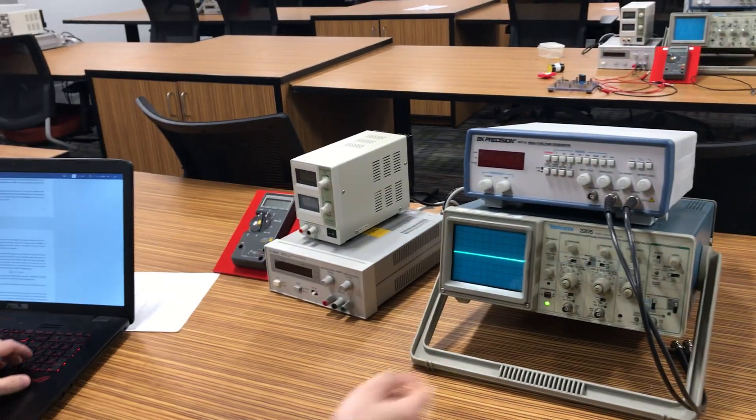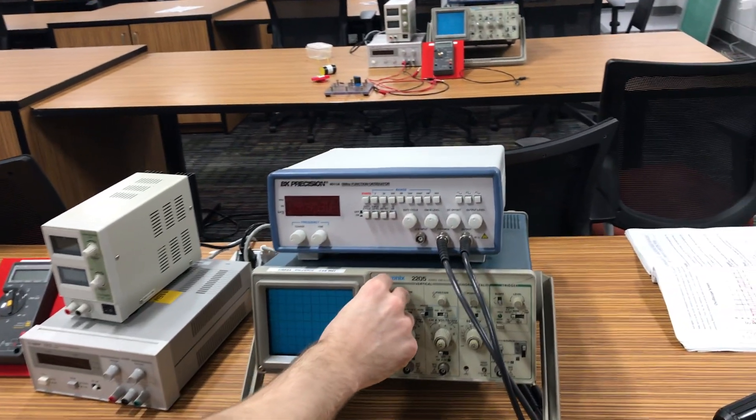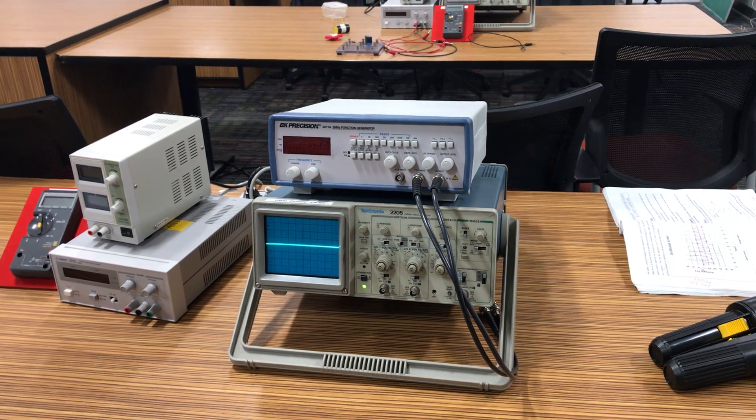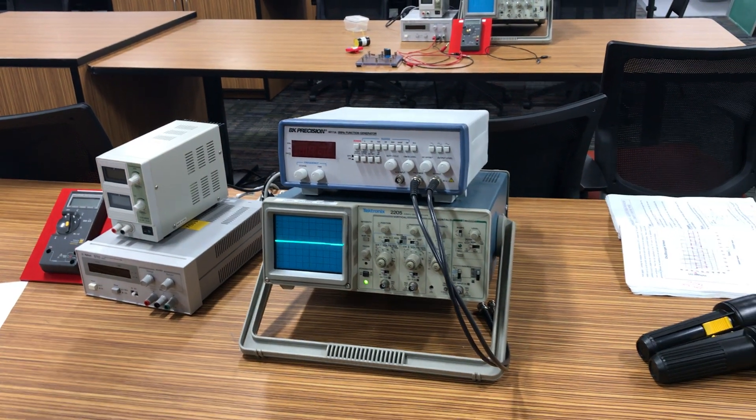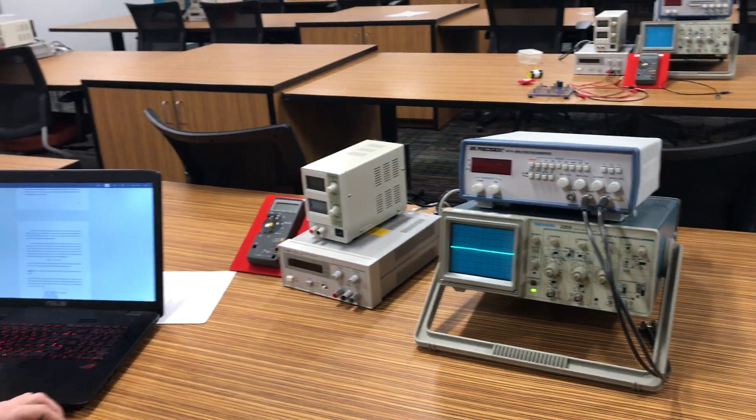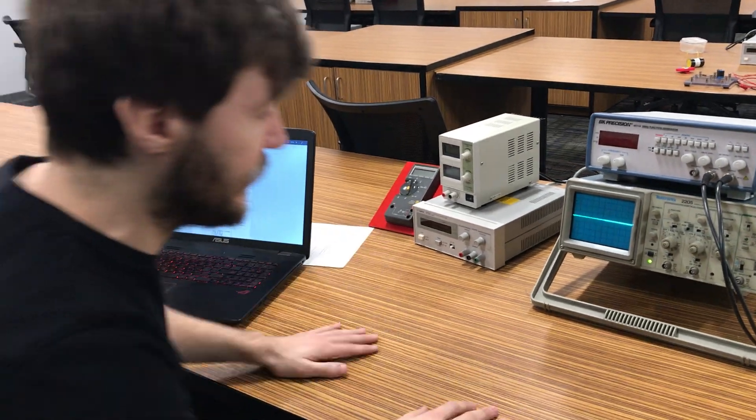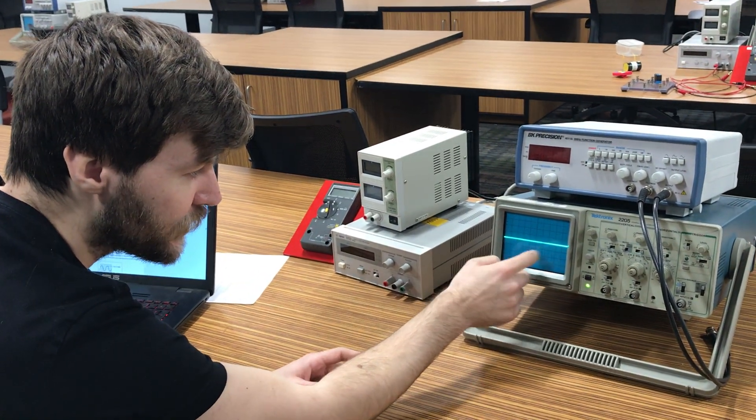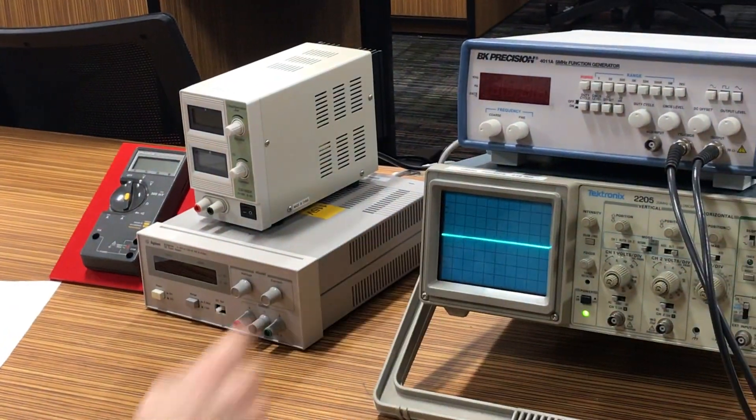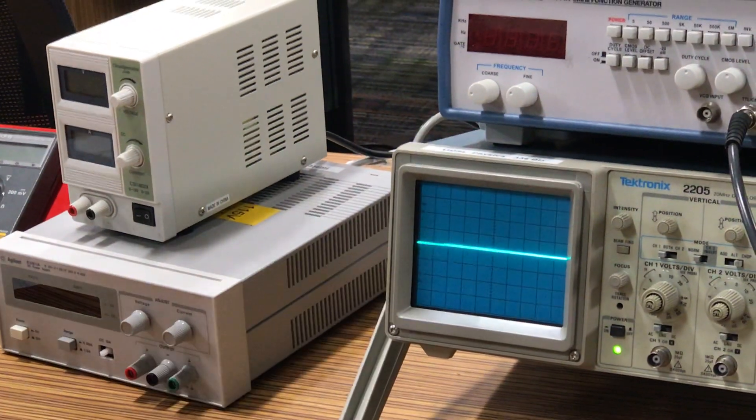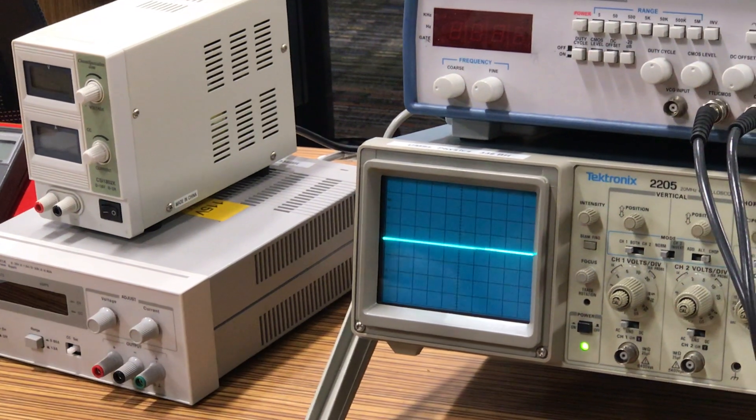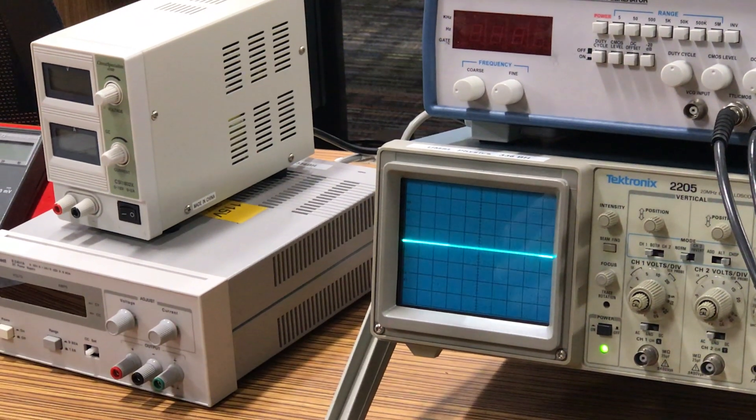We also have this intensity button that brightens or darkens what we're looking at, but what's really important to note is how to take readings on this thing. If you look here there's these little squares that are divided up on the screen and we're going to refer to each square as a division.